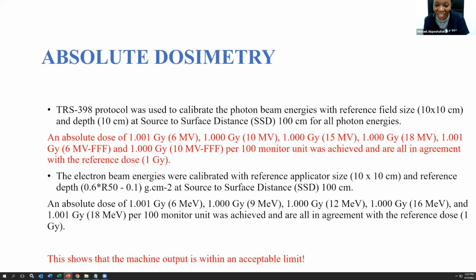The reference field size was 10 by 10 cm, and the SSD was 100 cm. Now, this is the result for the absolute dose that was obtained for all the energies, and everything is within acceptable limits. One gray was giving us 1 gray for all the energies, likewise for the electrons also. After all this, it shows that our machine output is within acceptable limits, looking at all these results that we have.